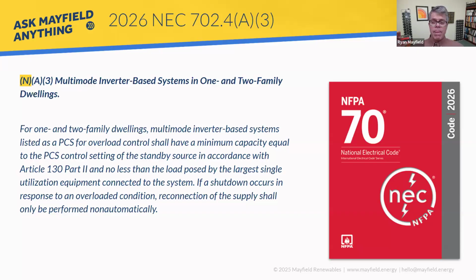So this got added in the 2026 language. And first off, you'll see it's for 1 and 2 family dwellings only. But we have this ability to have these multi-mode inverters listed as a PCS for overload control. That's one of the reasons why we spent so much time talking about PCS earlier. So we have this listing. You need to ask your manufacturer, great, you're listed at UL 1741 - is it for overload control?